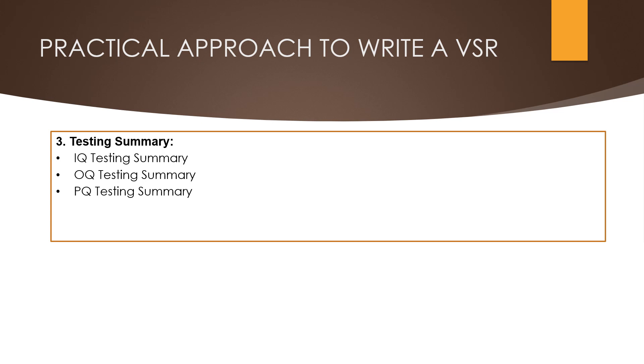Next is the PQ testing summary. Here we need to define the start date and completion date of performance qualification, and the performance qualification acceptance criteria which meets as per the PQ testing. We also need to define the key details of the PQ protocol number, status of pass or fail, and if any discrepancy is observed, the reference number of that discrepancy.